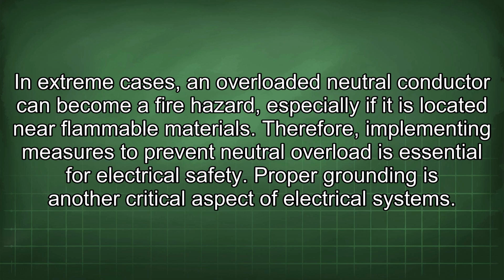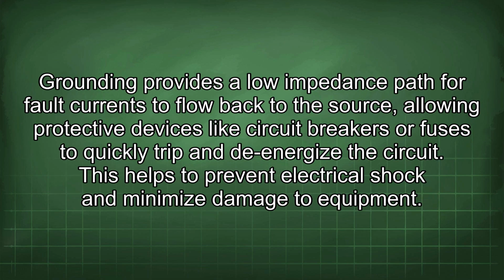Proper grounding is another critical aspect of electrical systems. Grounding provides a low impedance path for fault currents to flow back to the source, allowing protective devices like circuit breakers or fuses to quickly trip and de-energize the circuit. This helps to prevent electrical shock and minimize damage to equipment.